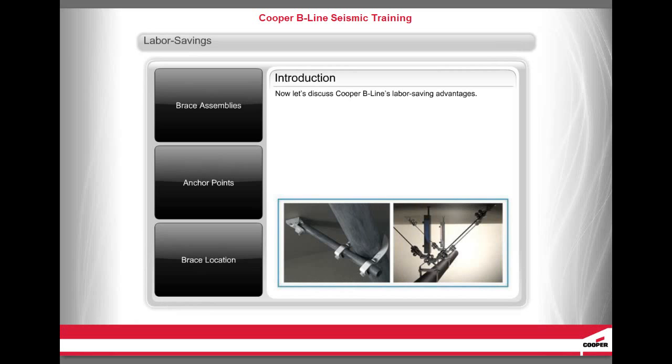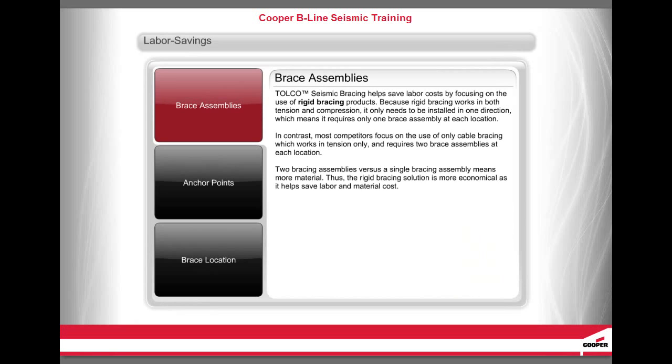TOLCO Seismic Bracing helps save labor cost by focusing on the use of rigid bracing products. Because rigid bracing works in both tension and compression, it only needs to be installed in one direction, which means it requires only one brace assembly at each location. In contrast, most competitors focus on the use of only cable bracing, which works in tension only and requires two brace assemblies at each location.